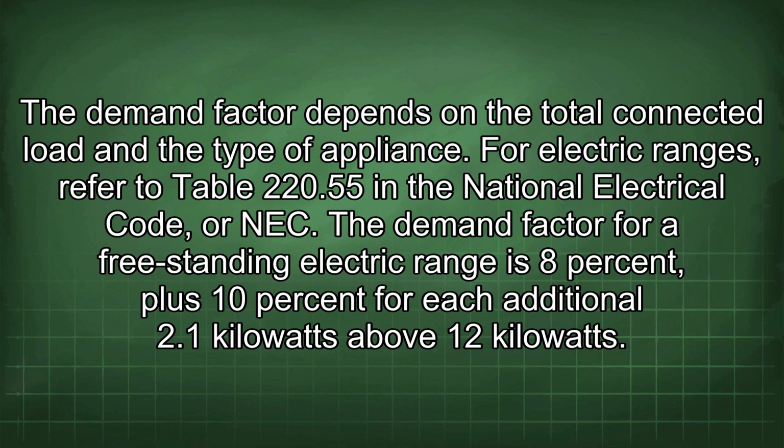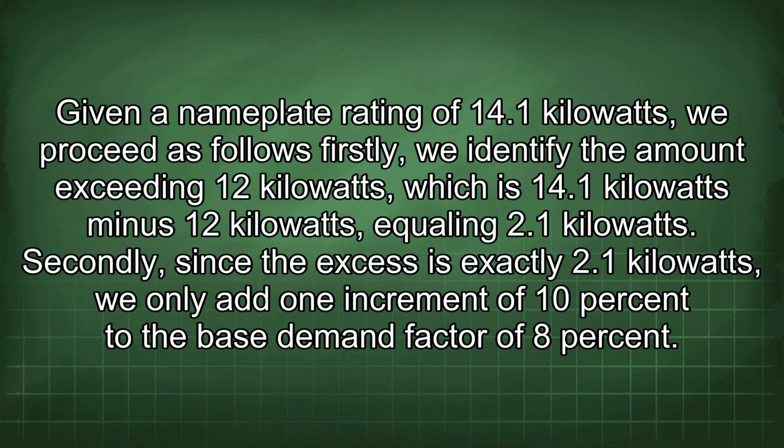For electric ranges, refer to Table 220.55 in the National Electrical Code, or NEC. The demand factor for a freestanding electric range is 8% plus 10% for each additional 2.1 kilowatts above 12 kilowatts. Given a nameplate rating of 14.1 kilowatts, we proceed as follows.